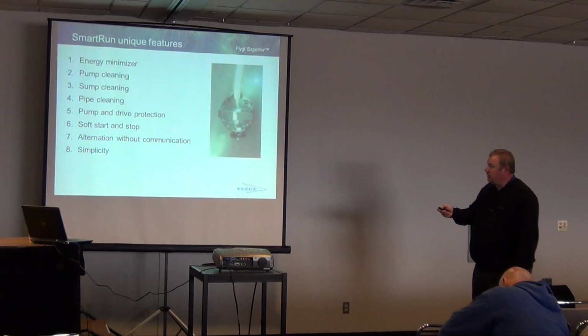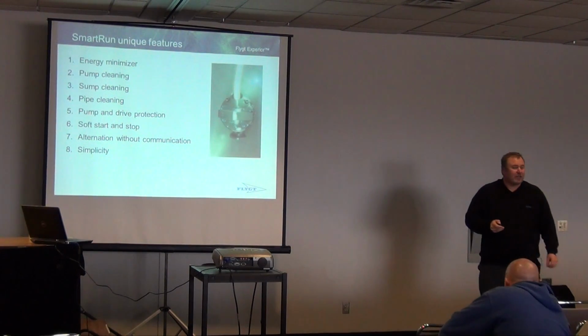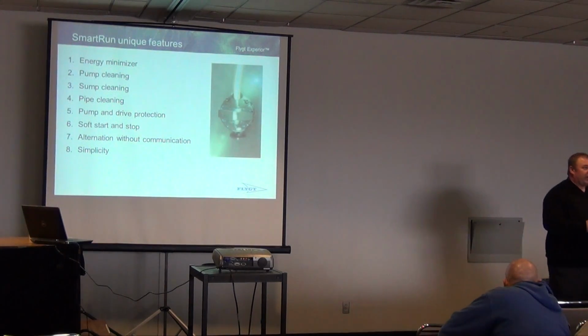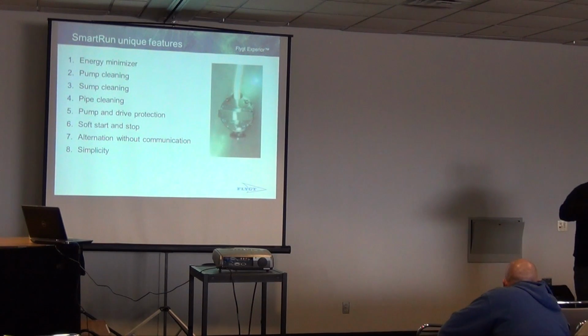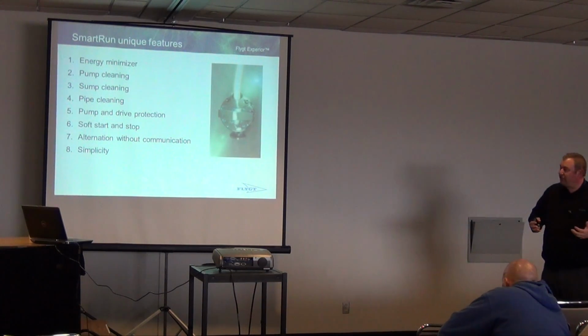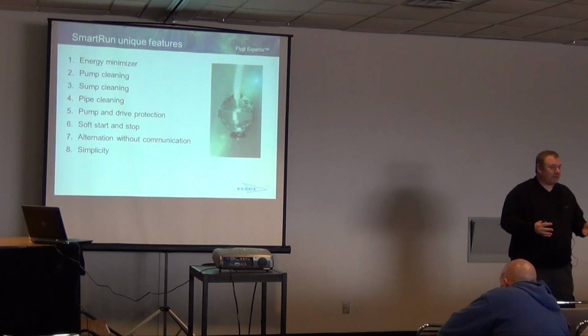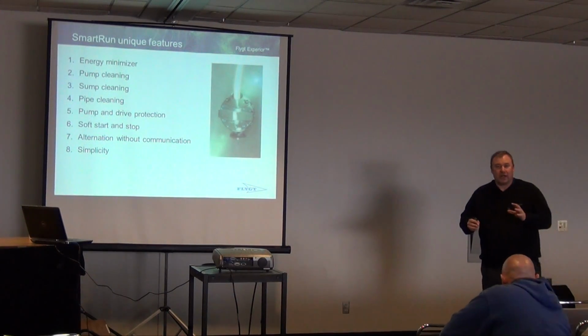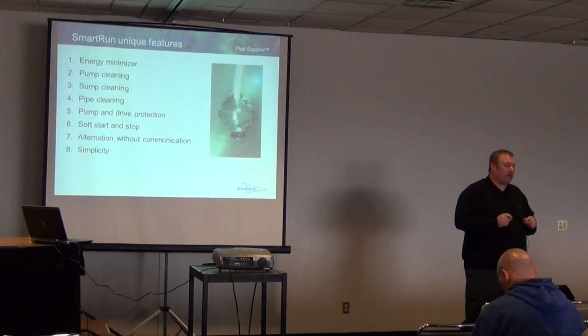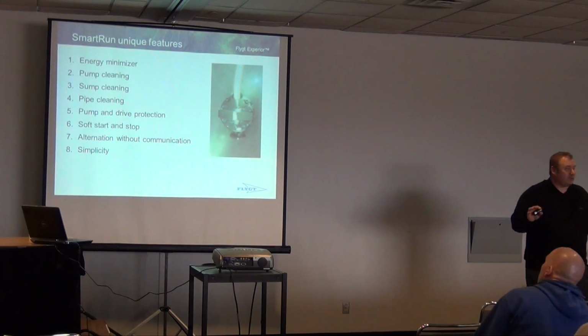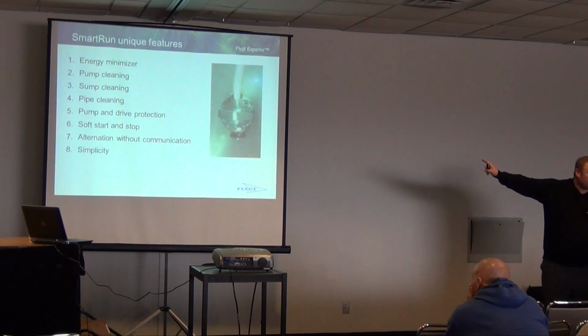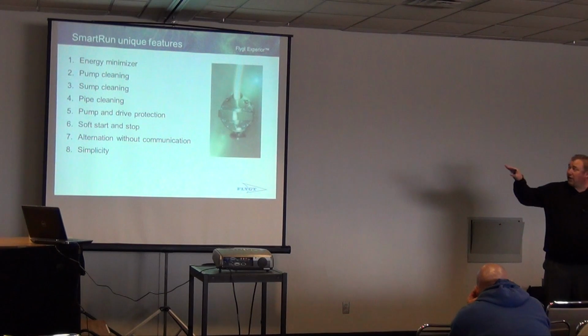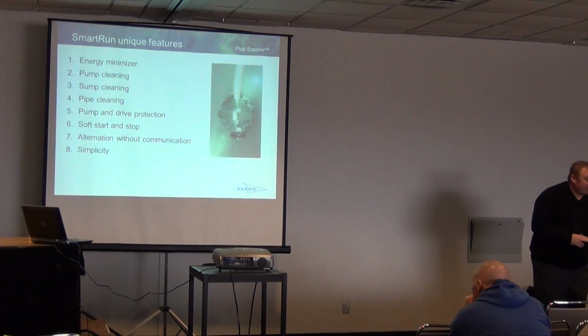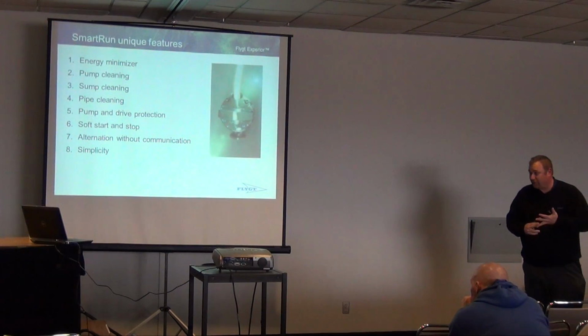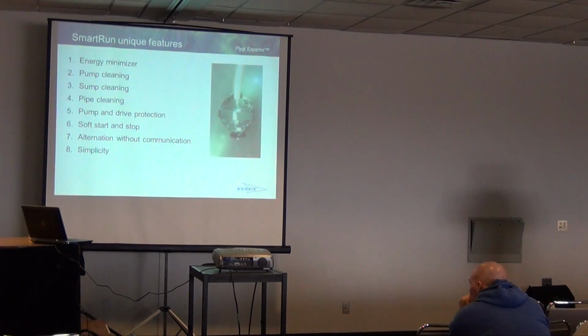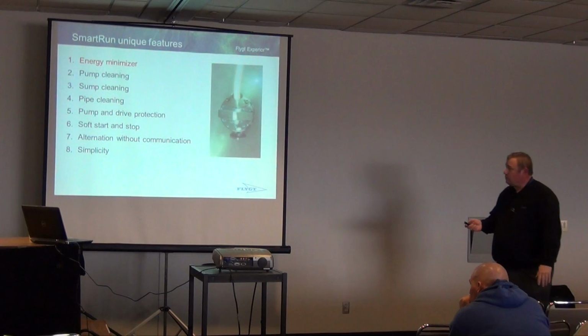We'll get into the alternation without communication, and it's very simplistic to use. Easy menus. Basically, it's what we call plug and play, like you have now with a lot of our computers and a lot of our electronics in the world that we live in today. It's a plug and play unit where it comes pre-programmed from the factory. It gets installed, you power it up, and if you want it to be as simple as pushing the start button and activating your station without doing anything, all that functionality and these wastewater algorithms are all going to be written into the program, and you're going to have all that functionality right away. You don't have to have anybody come out and program it. You don't have to pay high dollar amounts of labor to have somebody come out and do those sorts of things. It's done for you. So that's a nice feature as well.